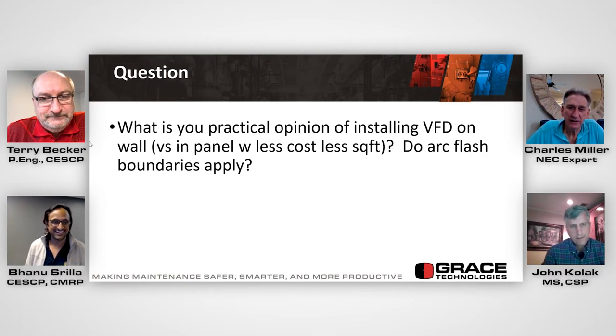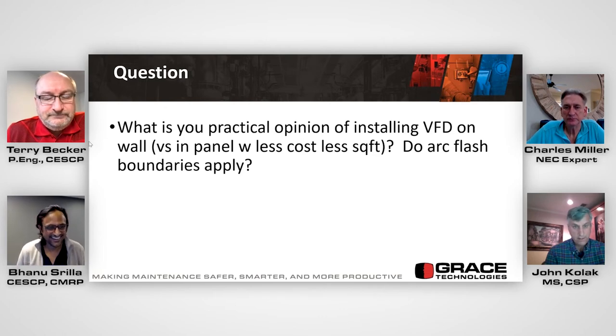It's the labeling thing I'm tripping over here. This doesn't affect labeling, but I still might have to label it if you're going to access it in the field. It's perfectly okay to have a label with a 0.0 calorie calculation, but what it's telling the user is that it's been considered. It's not a piece of equipment we didn't know was there. We've studied it and concluded there is no arc hazard, and everything Terry has said is right.